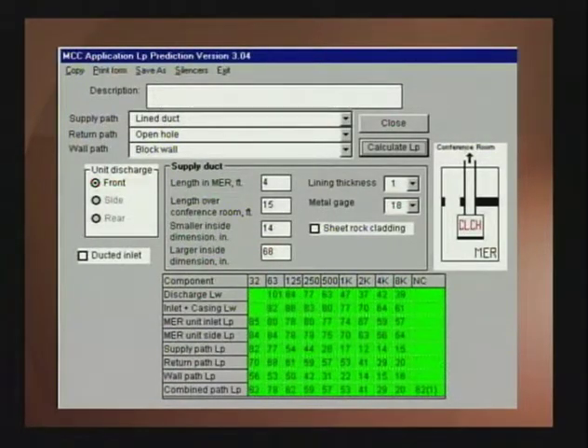CLCHLP provides predictions of the sound pressure level inside the equipment room around the air handler unit, and then provides predictions of the conference room sound pressure level determined by the three paths that sound is reaching the conference room. Supply path breakout, return path sound going through the open hole, and sound going through the wall path. Finally, the three separate paths are combined into an overall calculation of combined path sound pressure level with the resulting NC level. The advantage of having this kind of information is that the designer can quickly see which path is critical and apply noise control measures to the most critical path.